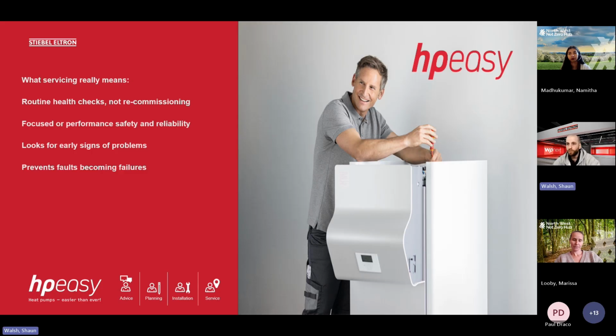If we were to service an air source heat pump, you would clean the evaporator of any debris, make sure the condensate drain is clear of any leaves so that the water can run off in defrost cycles. And then you may give it a visual inspection to make sure there's no leaks internally to the machine. But other than that, most of the servicing will be done on the system side of things. And when I say system side, I'm talking about inside the property, to do with pumps, filters, all those sort of components. Okay. So basically what servicing is doing is identifying any potential issues that would later become faults if they weren't addressed. Okay.